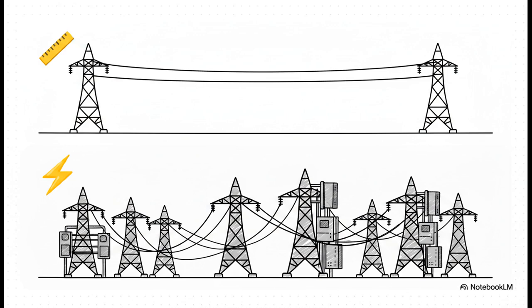And when we pit the two grid standards head-to-head out in the real world, 50 Hz comes out as the clear, undisputed champion for the long haul. A lower frequency yields a lower inductive reactance, which directly translates to a much better, far more stable voltage drop profile over massive distances. 60 Hz really suffers here. Its higher inductive reactance means much larger voltage drops, which basically forces utility companies to either build substations closer together, transmit at dangerously higher voltages, or install extremely expensive capacitor banks just to keep the power stable.